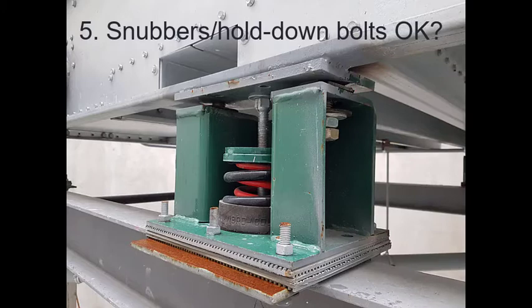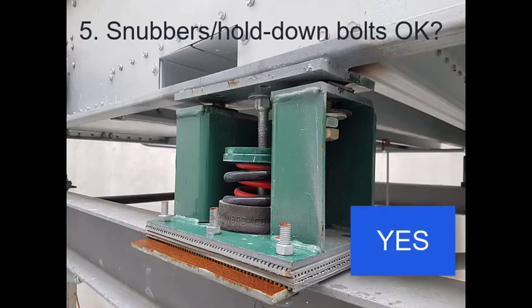The rubber hoses may have been pushed out of position during installation, and it would be better if they could be pushed back into place, since they are needed to help prevent metal-to-metal contact during seismic and significant wind events. However, this particular tower has no seismic restraint requirements and is well protected in a full enclosure, so the position of those rubber hoses is much less important, and so this question can be answered with a yes, since it's close enough.